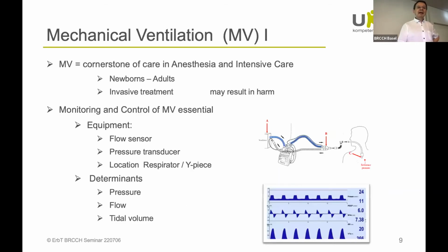Now, mechanical ventilation is certainly a cornerstone of care in anesthesia and intensive care. It's applied to newborns or prematurely born infants to adults, and it's no doubt an invasive treatment that may cause harm. Therefore, we need control and we need monitoring. That is really essential. Now, the equipment that is used to do this are flow sensors and pressure transducers.